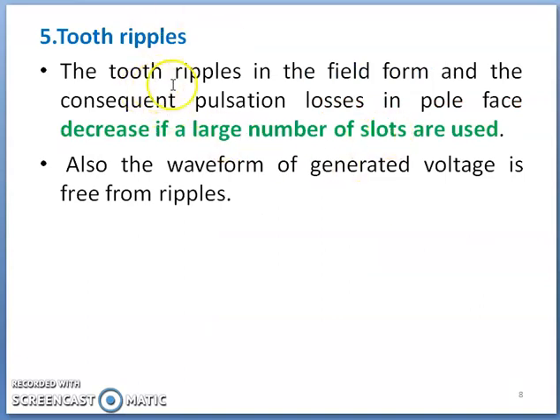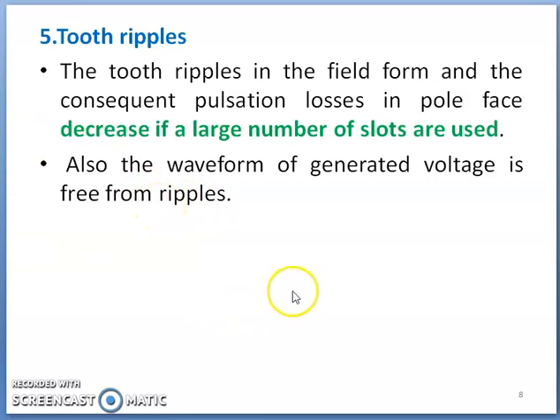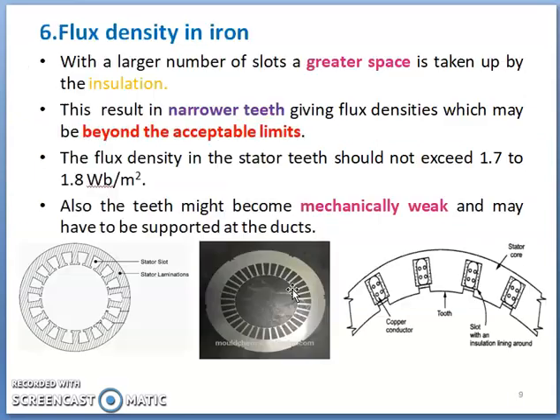Regarding tooth ripples, the tooth ripples in the field form and the pulsation losses in the pole face decrease if a larger number of slots are used. When the number of slots is more, tooth ripples as well as pulsation losses decrease, and the generated waveform will be free from ripples — close to a sine wave — due to the larger number of slots.